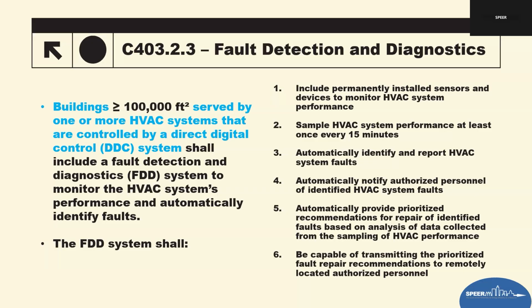It's going to actually look at temperature or contact closures and convert that into signals that can now be monitored in real time. The intent of the requirement, of course, is that large buildings have higher energy losses when HVAC issues go unnoticed. That's where the code's starting to tighten up. Not looking at just efficiencies of the equipment, but let's figure out faults and errors and equipment that is falling apart, basically, or having something that's breaking down. Let's realize that early on before it goes too far.